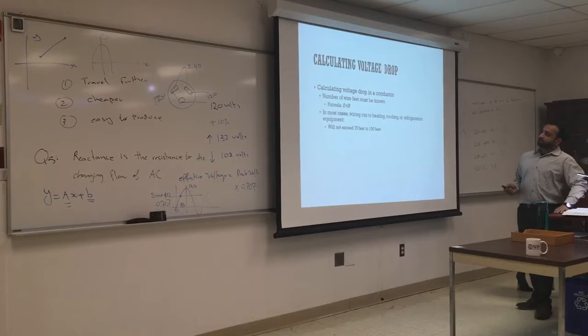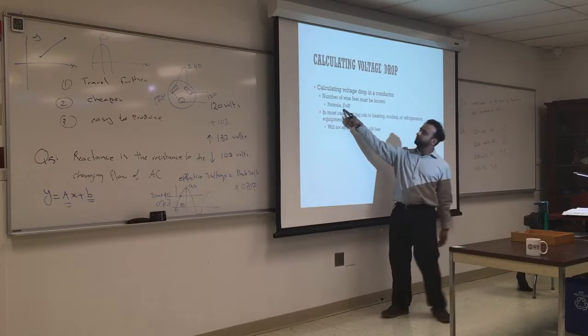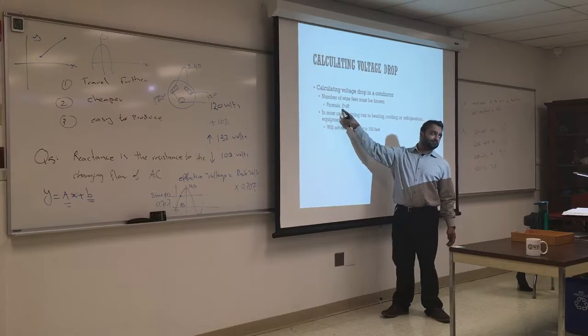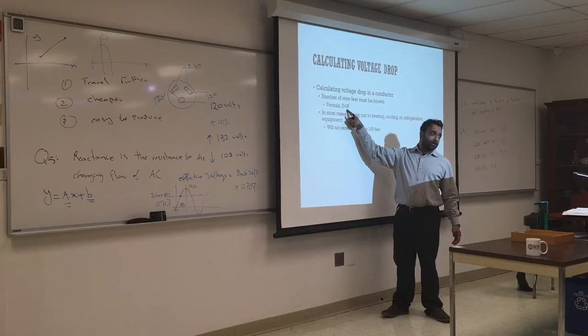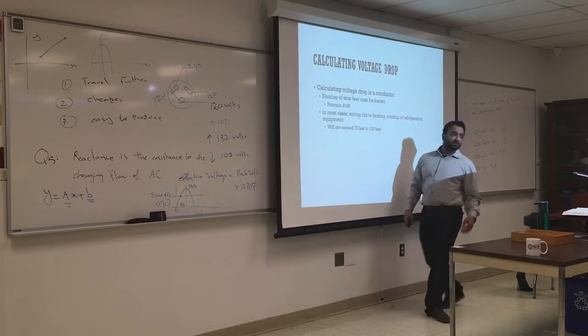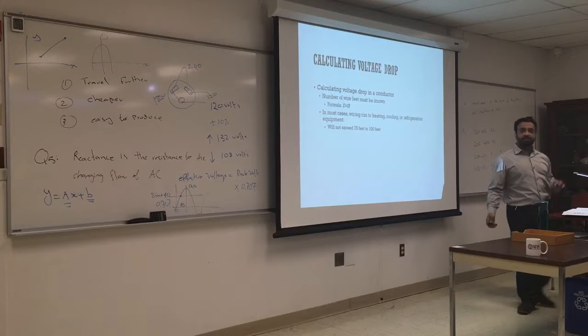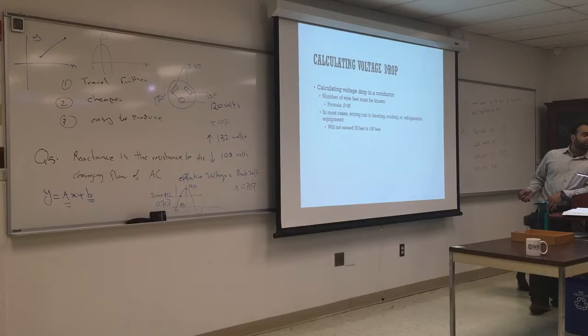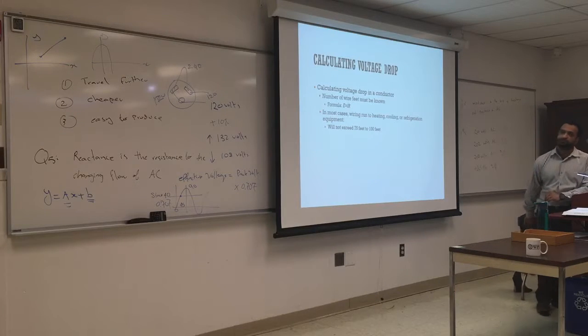Calculating voltage drop in a conductor, the number of feet of wire must be known. This is E: voltage equals amperage times resistance. So you can get the resistance and see what voltage is running through the equipment and deduct that. In most cases, wiring run to heating, cooling, and refrigeration equipment will not exceed 75 to 100 feet, which is around 30 meters. That's something you have to look at.